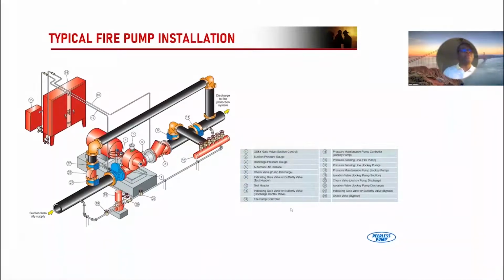I had to put in here a basic installation of an electric fire pump. When I was talking about accessories earlier, you can see that here is your fire pump electric motor. Here is your pump, and here's your isolation valve at the suction side of it. Here's a check valve on your discharge. Here's your bypass loop over here. This will be required in some areas where you have a supply like from a city, like 50, 60 PSI. The whole idea there is if you lose power to your pump, you can just bypass it, so your fire system will still at least have 60 PSI going into it. And you have your electric controller, a little jockey pump over here, and your test header here.